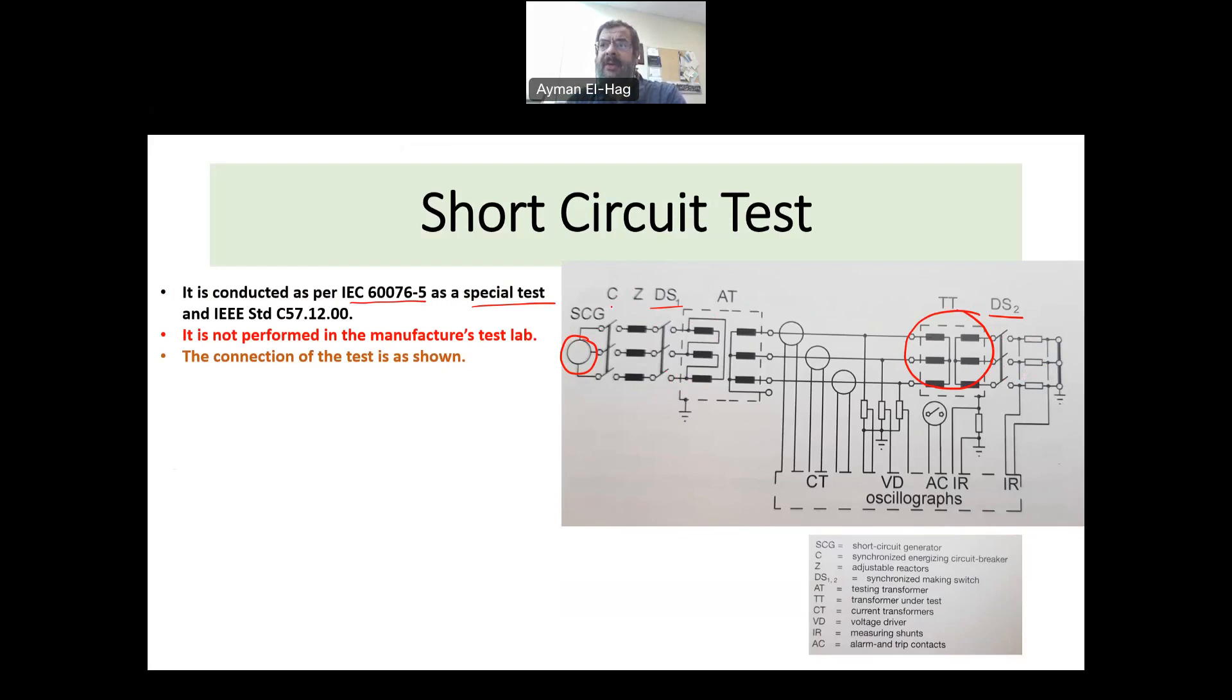The second version, which is the more preferable one, the more realistic one, you energize the transformer. So DS1 will be normally closed and this will be open. And then you close this to simulate as if the transformer is energized and then a short circuit happens to its secondary.